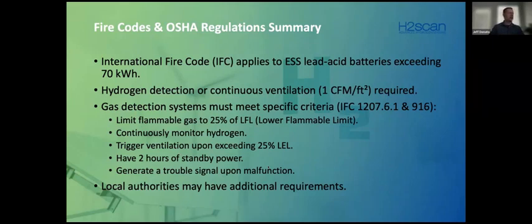Then it also has to trigger the ventilation fan or the gas purge system. And then you also have to have 2 hours of standby power for the system. And as I mentioned before, with NFPA 76, you have to generate a trouble signal upon either malfunction or alarm. And so that trouble signal needs to go to either like a network ops center or a fire alarm panel. And local authorities may have additional requirements.